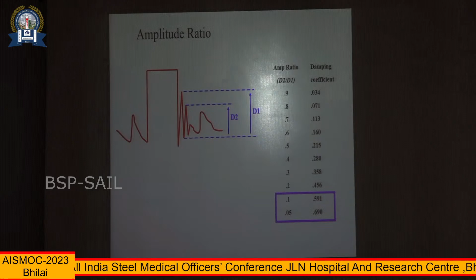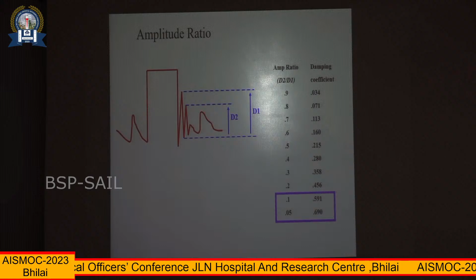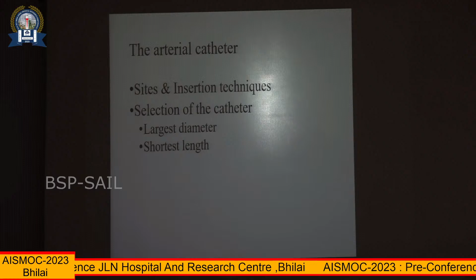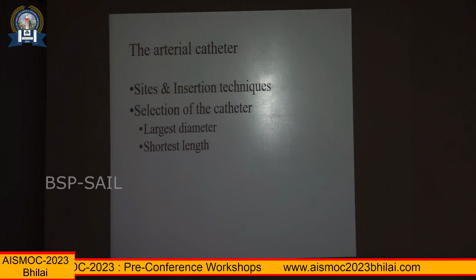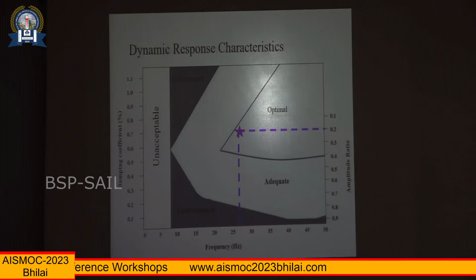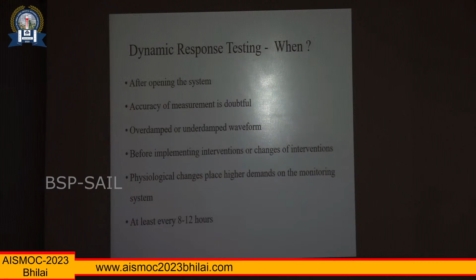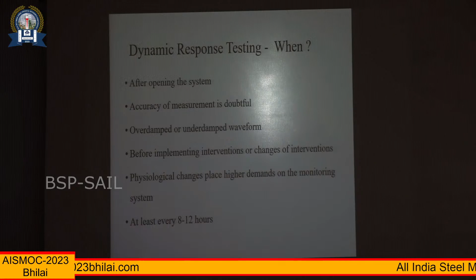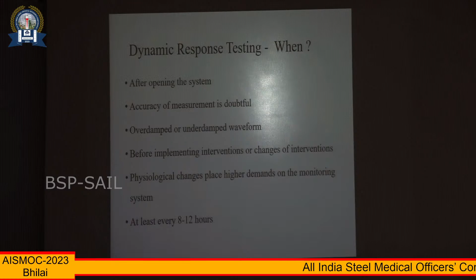Like I said, you look at the ratios between the second and the first wave, and you can get the amplitude ratio or the damping coefficient. We've gone through this. What are the prerequisites for having an optimal system? You choose the arterial catheter appropriately. You choose the length. You use low-compliance tubing, and so on. Don't allow clots in the system. You can have charts for optimal damping, but these were more relevant when we had to do the manual preparation of the transducer. They may not be applicable now because we have ready-made transducers.